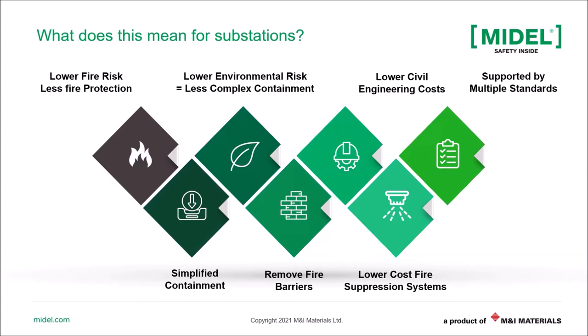It would also lower the environmental risk. What I mean by that is if there's a spill, the remediation cost and the reclamation cost would be much less compared to mineral oil. And as I had shown earlier, the civil engineering costs would be less when using an ester liquid. The reason for that is because you would be saving money in not having firewalls around the transformer, the containment system would be smaller, and the real estate around the transformer could be used for other applications rather than just being space required for the containment.